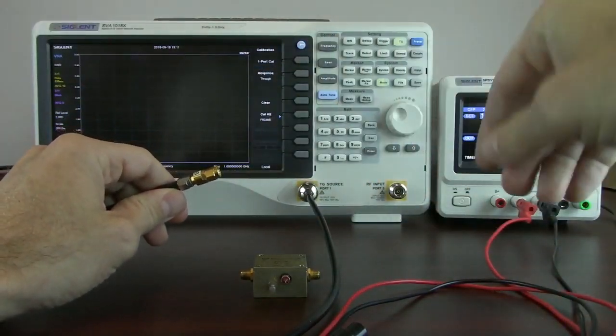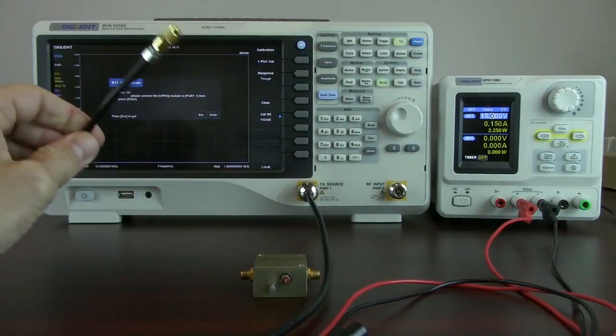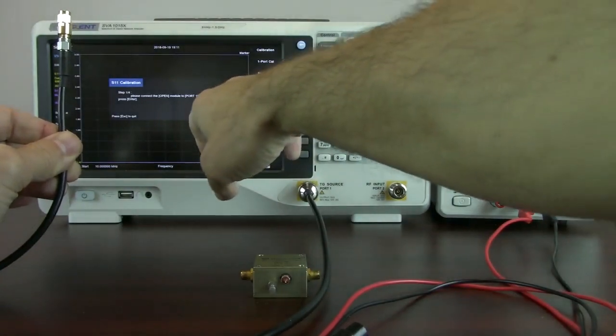Now I'm going to go to calibration and I'm going to perform one port cal. Now it's going to ask me please connect the open module. We're just going to leave it open and hit enter.